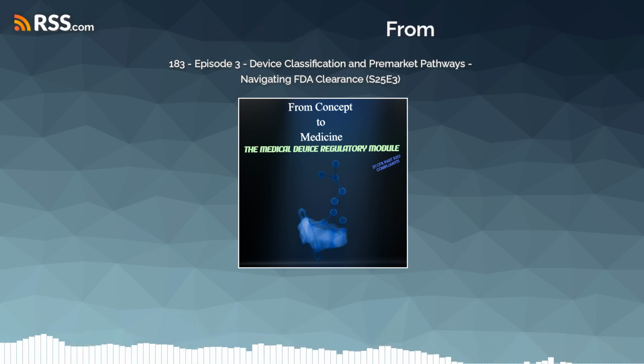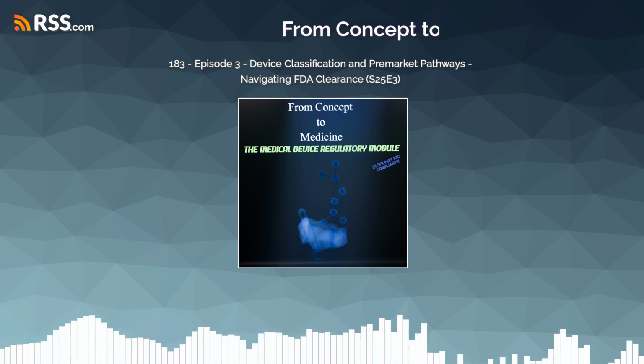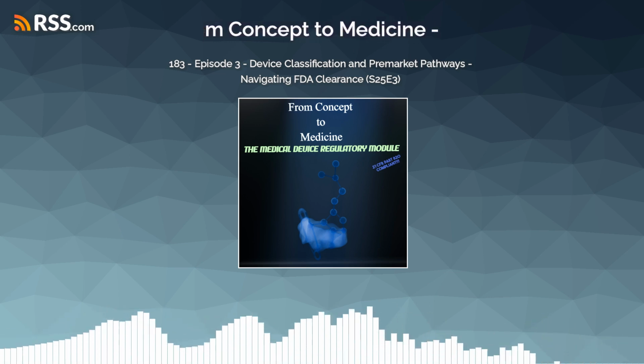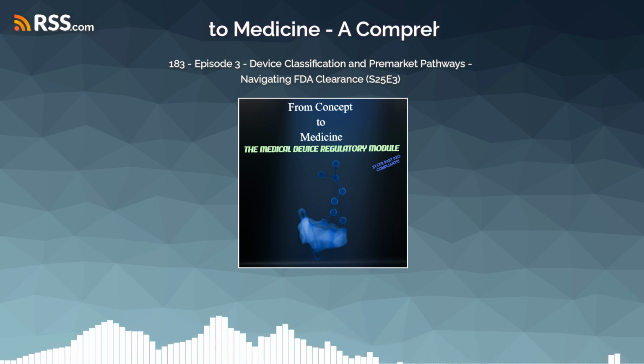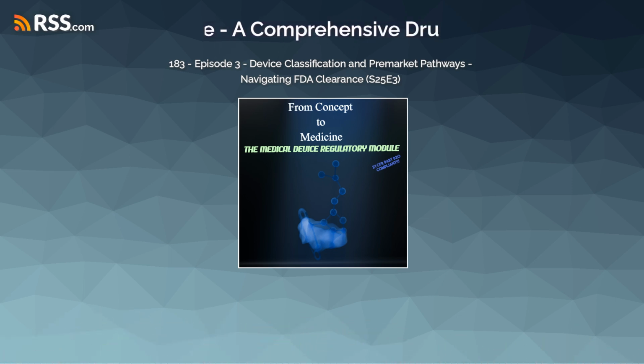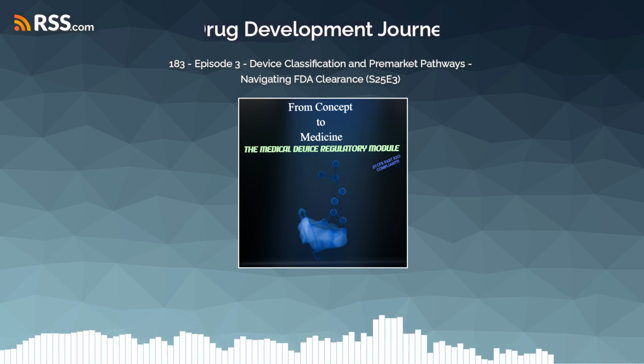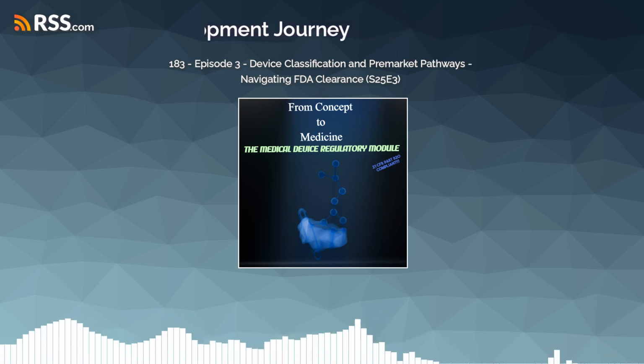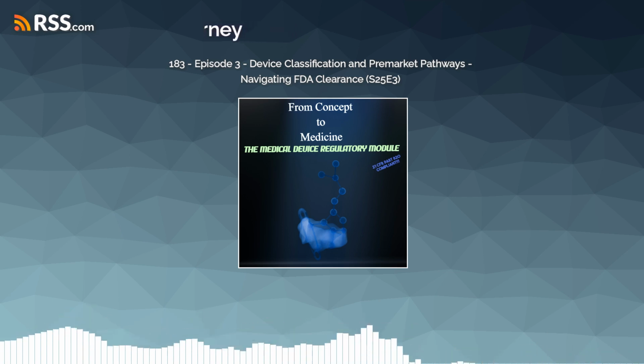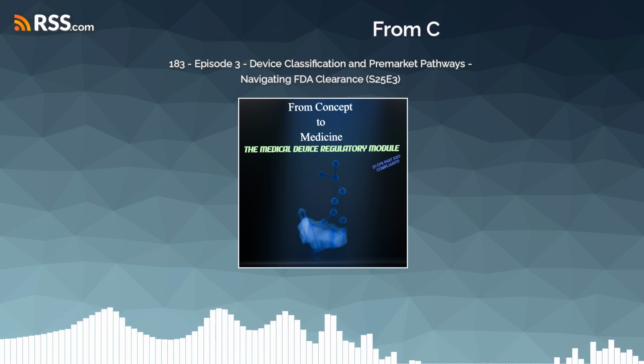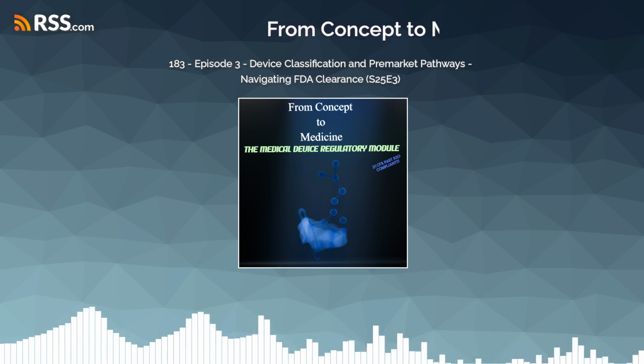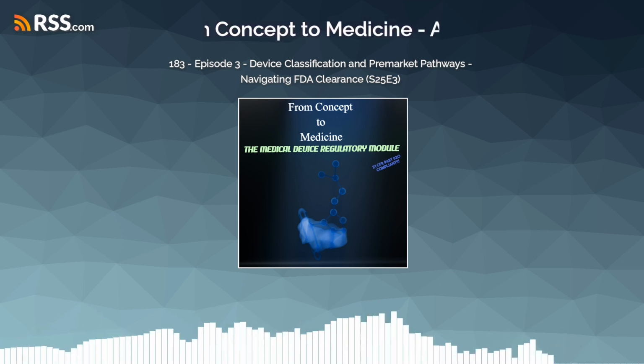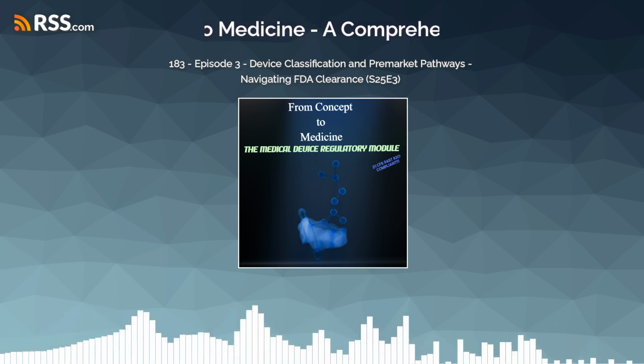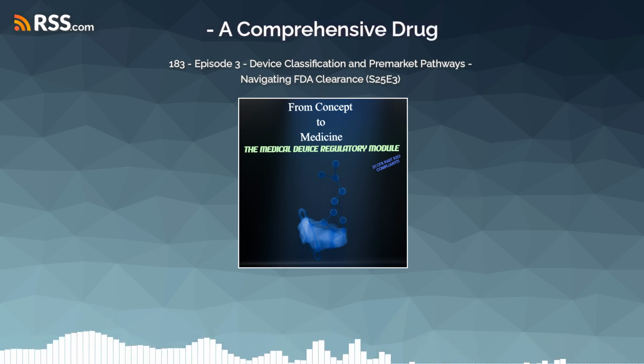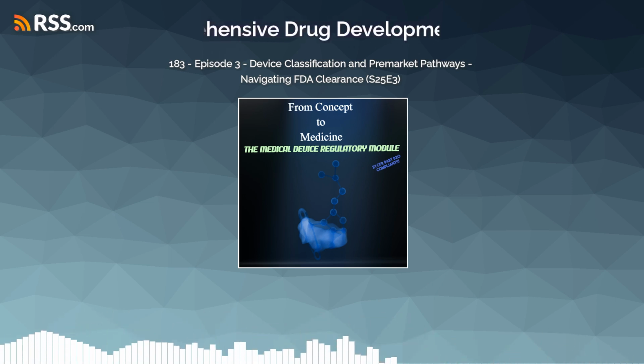Okay, let's start at the bottom then. Class 1, low risk. What does that entail? Class I devices are the lowest risk category. They're subject to what the FDA calls general controls. Think of general controls as the universal baseline rules. They apply to all devices. They cover things like the quality system regulation, that's 21 CFR Part 820, basically the FDA's rule book for how manufacturers design, build, and monitor devices. Plus strict rules for labeling, 21 CFR Part 801, and reporting serious problems, which is medical device reporting, Part 803.